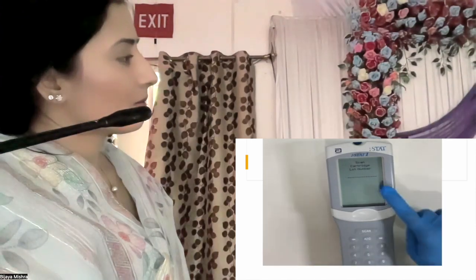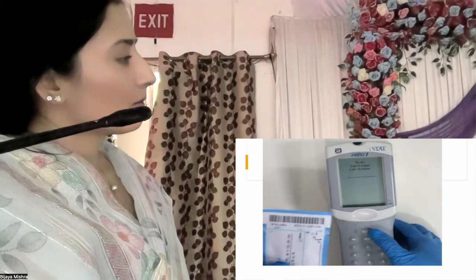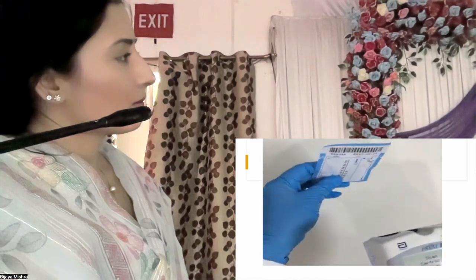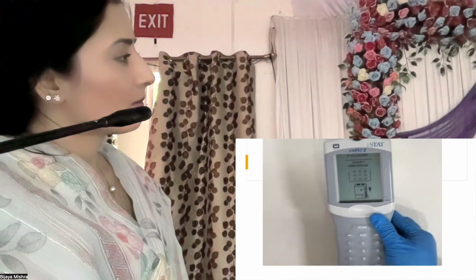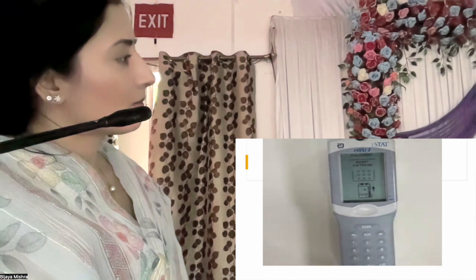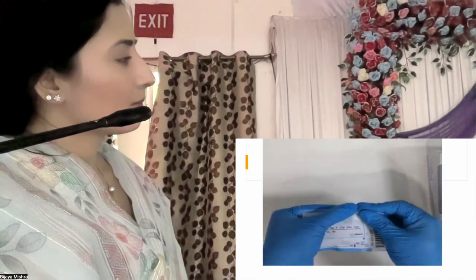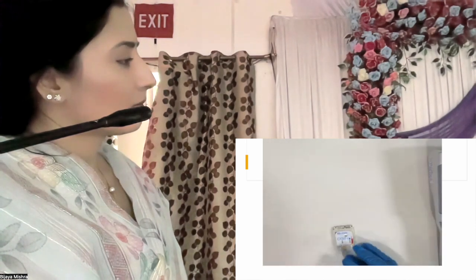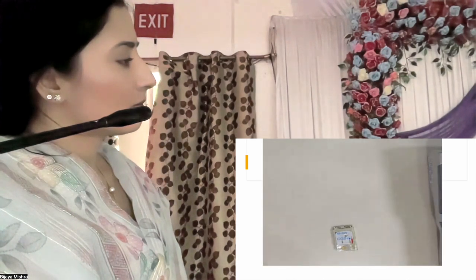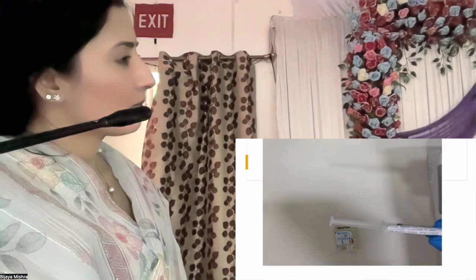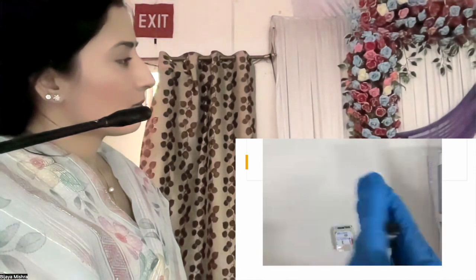We then scan the cartridge lot number, which is on the package insert of the cartridge. This here is a cartridge. We will be using an arterial blood gas sample, which is in a heparin coated tube, syringe.